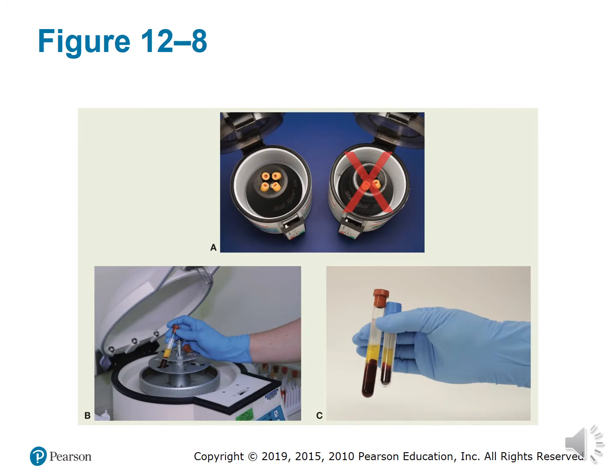When placing tubes in the centrifuge, you have to make sure that the centrifuge is balanced, or otherwise it will not spin the tubes down. If that centrifuge is not balanced, it will not work. It's going to rattle all over the place, make a lot of noise, and you will tear it up. And centrifuges cost on average about $2,000 to just have fixed. $2,000, right? So be mindful of that when working with a centrifuge.